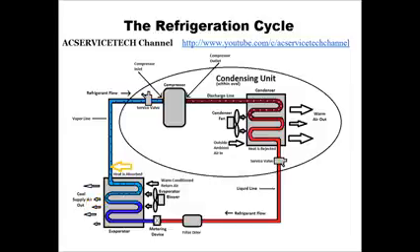As it comes out of the evaporator coil, the temperature increase from the end of the saturated state in vapor to where it comes out is called the superheat. If you continue along, you keep coming up as a low pressure, low temperature vapor. You come up, make a right, and come over to the service valve. That's where we take a superheat reading.